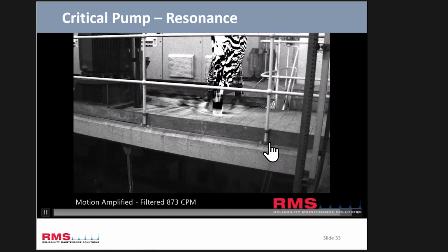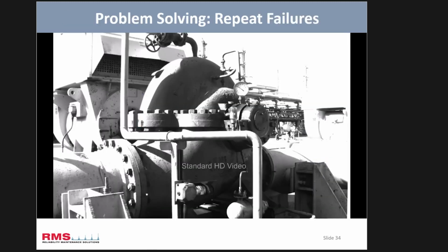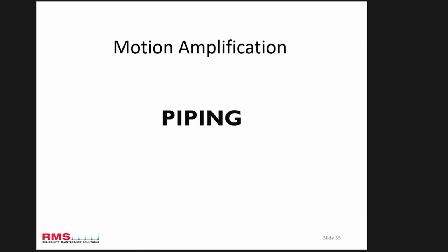So you can see the filtered response. So that's a good tool to do once we do bump tests. You can see how we use the camera to highlight the frequency of concern, really. Again, this is a problem solving of a pump.